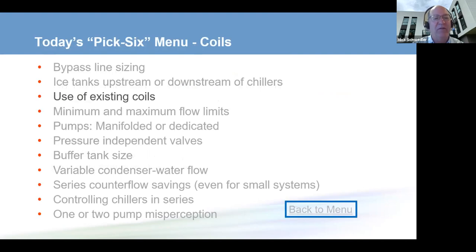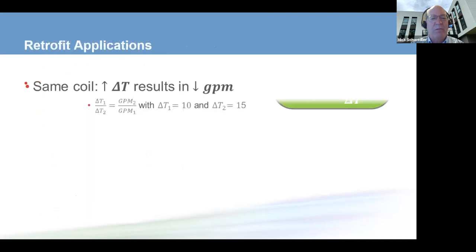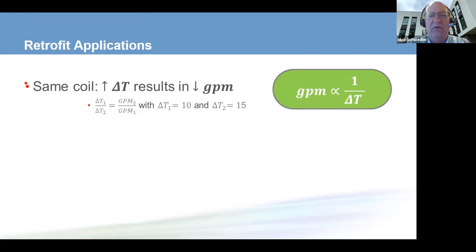Let's see what the Board of Governors picked next. Use of existing coils. A lot of people think that coils are designed for a particular delta T. I tell people coils are just dumb pieces of metal. They don't know anything. Their job working with a control valve is to transfer heat. So if we give a coil colder water, it will use less of that water and the return water temperature will go up. So coils aren't designed for a particular flow rate and delta T.